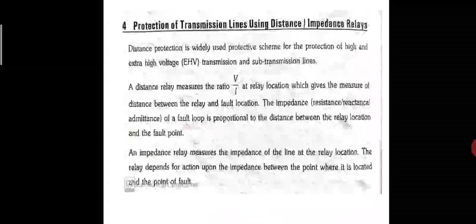Next one, protection of transmission lines using distance or impedance relays. Distance protection is a widely used protective scheme for the protection of high and extra high voltage transmission and subtransmission lines. A distance relay measures the ratio V by I at the relay location, which gives a measure of the distance between the relay and the fault location. The impedance, meaning resistance, reactance or admittance of a fault loop, is proportional to the distance between the relay location and the fault point.